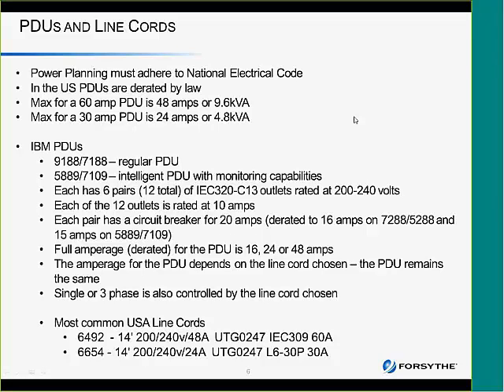And then for a 30-amp PDU, you can't plan for more than 24 amps or 4.8 kVA. So those are your planning points, and that's what I build into my planning spreadsheets when I plan for PDUs. The IBM PDUs come in two flavors. There's the 9188, 7188. Those are feature codes, and that's just a regular PDU. And it can handle, as I said, the 30, 60, or it can actually take a three-phase input.